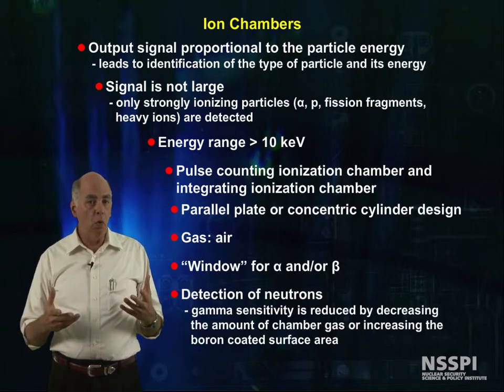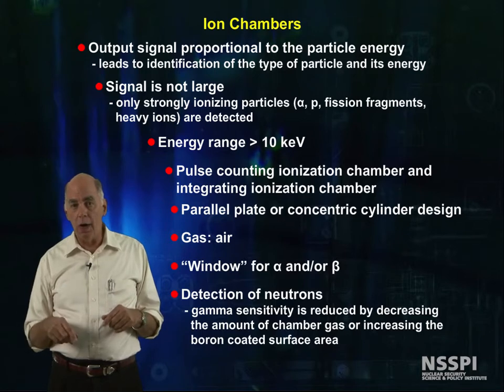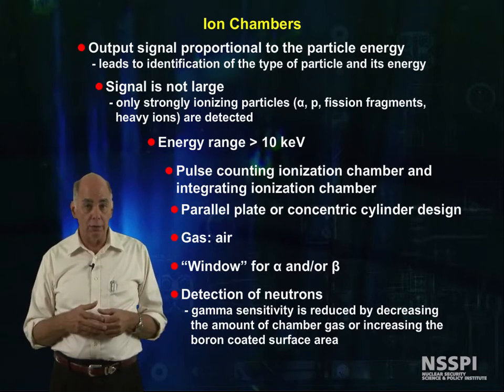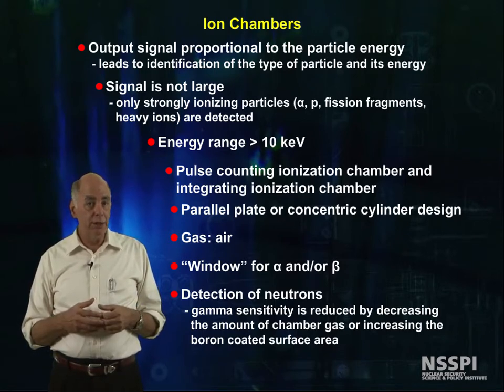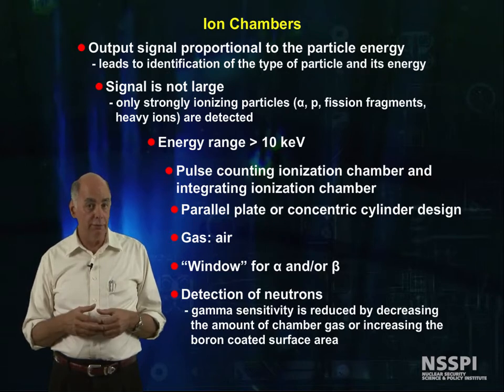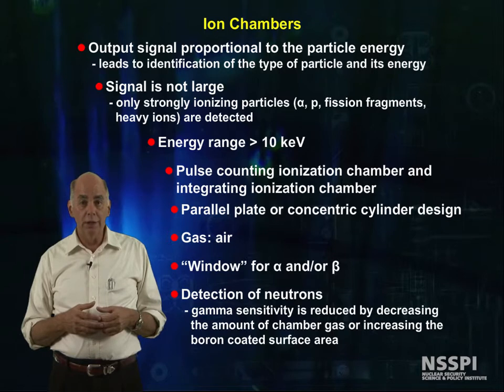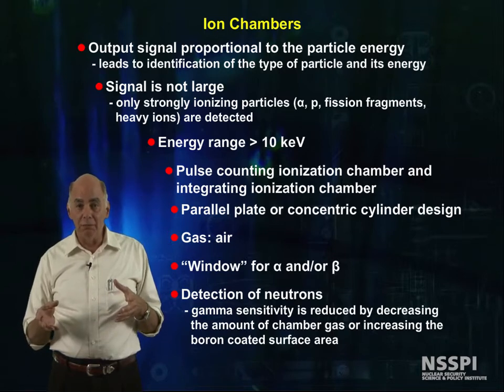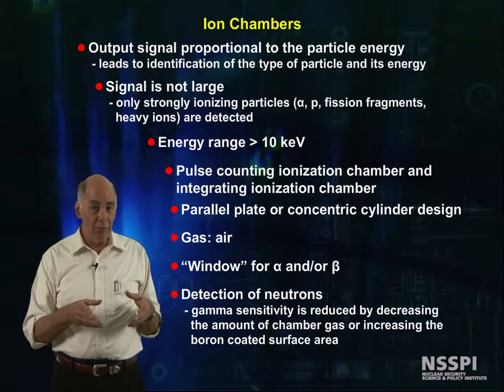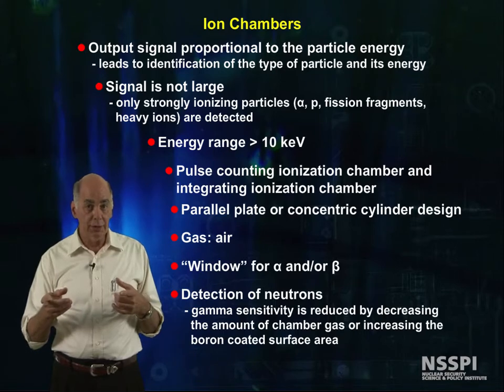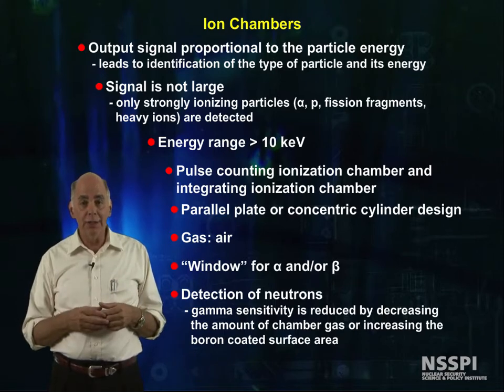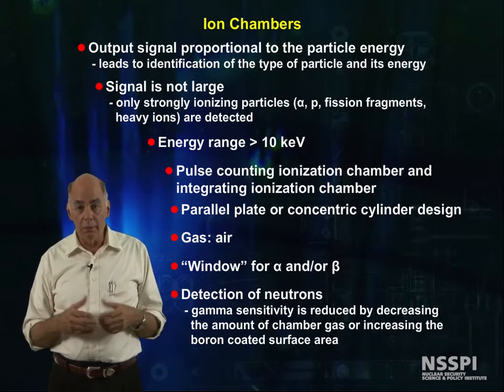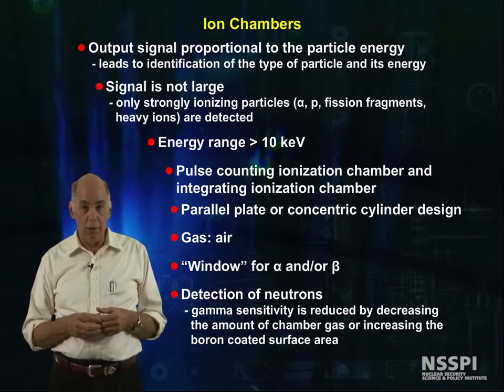If boron is added to the sensitive volume, then neutrons interact with this boron and create charged particles. These detectors can be used to monitor neutron fluence rates at a reactor, for example. There are several design paths to minimize the interference of gamma rays with these detectors, including decreasing the amount of chamber gas or increasing the amount of boron, among other ways. We'll talk about it more in a minute.